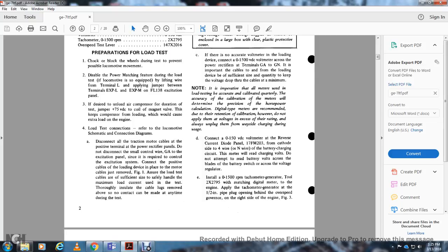Prepare for loading test. Block the wheels during the test to prevent possible locomotive movement. The power matching feature is desirable during the load testing if the locomotive is equipped. Lift the wire of terminal L and apply a jumper between terminals EXP-L and EXP-M on the FL138 excitation panel. If desired, unload the compressor for the duration of the test with the jumper to positive 75 volt DC to coil of magnet valve. This keeps the compressor from loading, with regard to the extra load on the engine. For load testing connections, refer to the locomotive schematic connection diagrams.